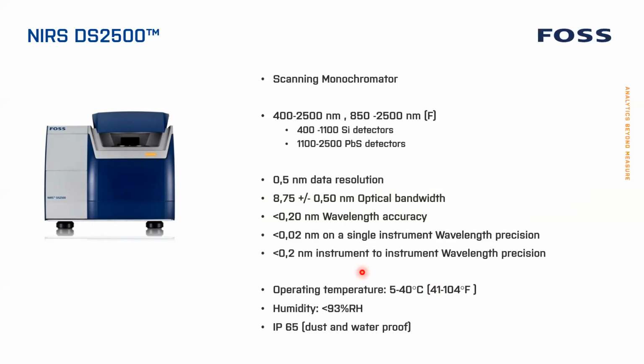Then if we look at some of the specification here, the 0.5 nanometer data resolution is how wide the steps are when you collect the spectra and you export it. So when you look at the spectra, there will be points with 0.5 nanometers difference. Doesn't make any difference really to how the instrument performs. The important thing is what's called the optical bandwidth, which is 8.75. That is how wide a peak is when you measure it. If you have an infinite small peak and you measure that, that will be 8.75, halfway up to the top.